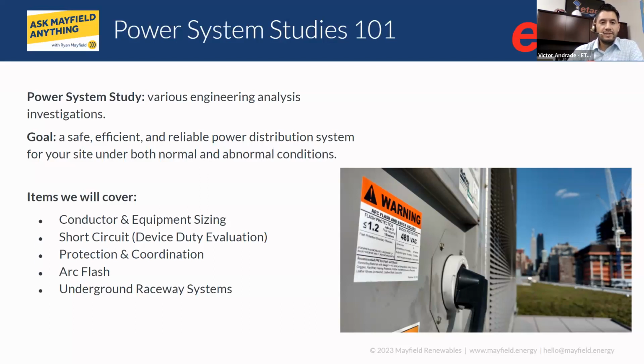We could probably talk about 60 or more power system studies that can be performed, but the scope of work for today is going to be the bread and butter that most of us do on a daily basis. So these cover the conductor and equipment sizing, the short circuit analysis, and also the device duty evaluation, protection and coordination. Clayton will talk a little bit about arc flash. I'll tie it in with battery energy storage. And then Nick will cover underground raceway systems. So these are basic power system studies that you'll find in NEC, IEEE color books, and other standards and requirements.